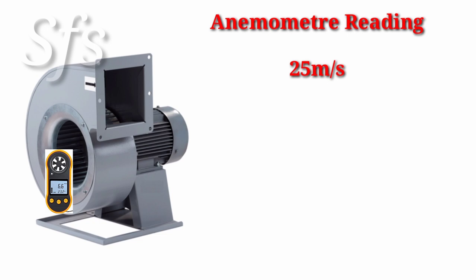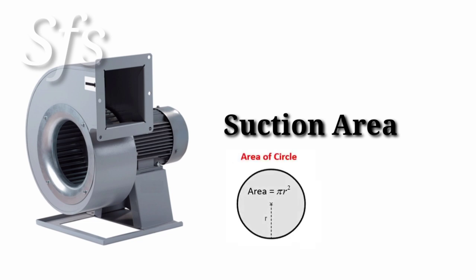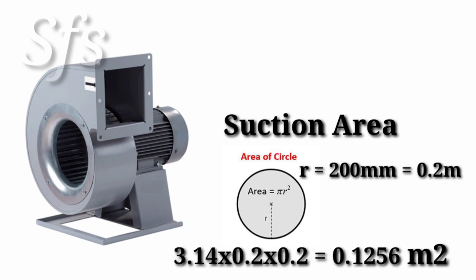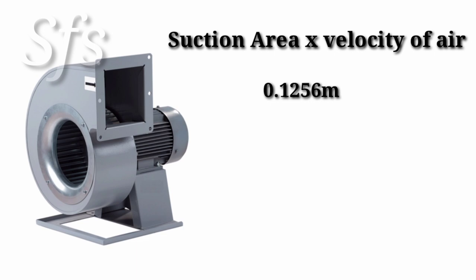Now, second step: we have to calculate the suction cross-section area. Suction cross-section area is circular, which is calculated by the formula pi r square. Suppose the radius is 200 mm, which means 0.2 meter. So by the formula pi r square, the cross-section area of suction is 0.1256 meter square.